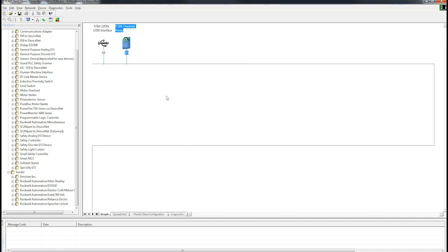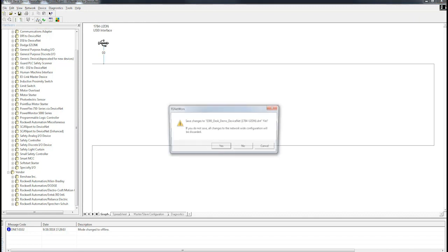And one thing again to note with the DeviceNet interface, since this change was made online, you basically have to take the component or the system offline, delete the node, and then rescan the nodes to reinitialize your network and redetect the devices that are on there. So if we hit delete, and then we do a rescan, the device should now show up as an E3 Plus 9 to 45 amp device.